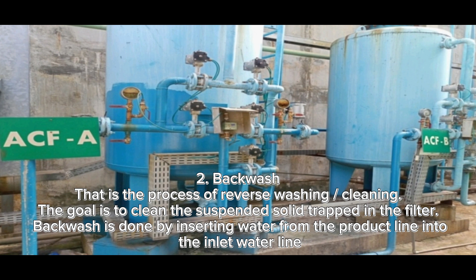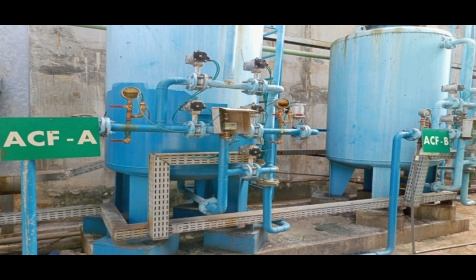That is the process of reverse washing or cleaning. The goal is to clean the suspended solids trapped in the filter. Backwash is done by inserting water from the product line into the inlet water line. Number 3, rinse. The rinsing process is intended to remove the backwash water and remaining suspended solids.